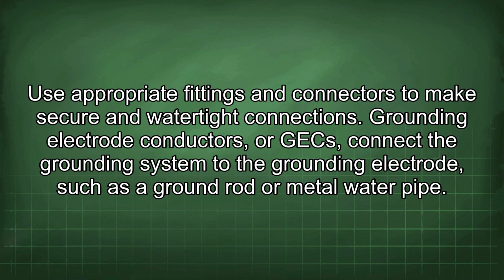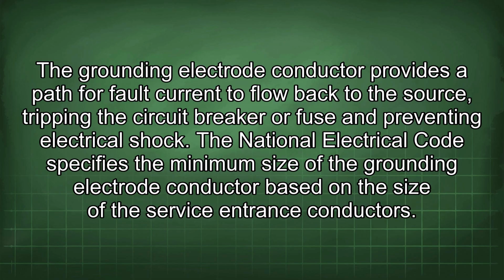Grounding electrode conductors, or GECs, connect the grounding system to the grounding electrode, such as a ground rod or metal water pipe. The grounding electrode conductor provides a path for fault current to flow back to the source, tripping the circuit breaker or fuse and preventing electrical shock.